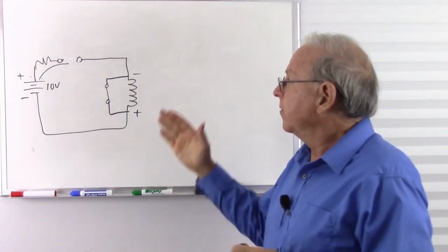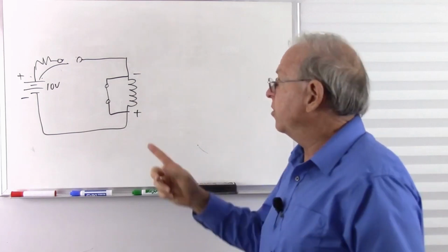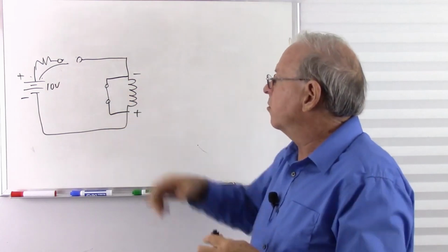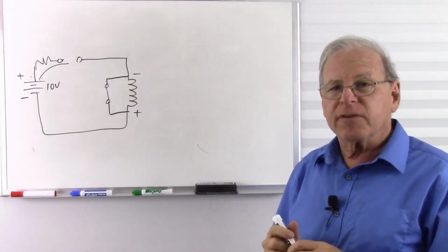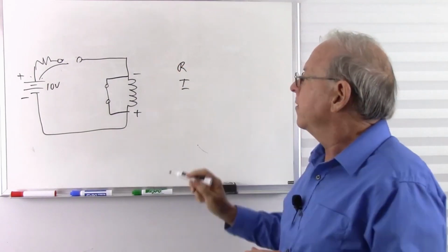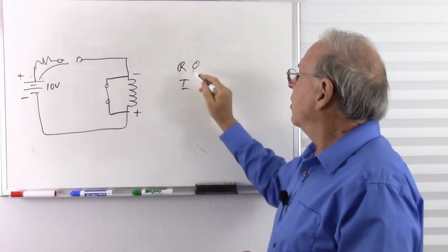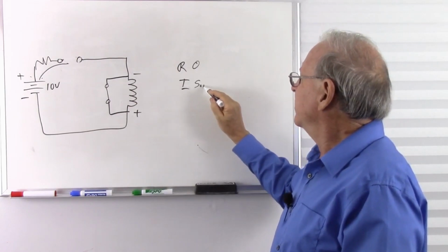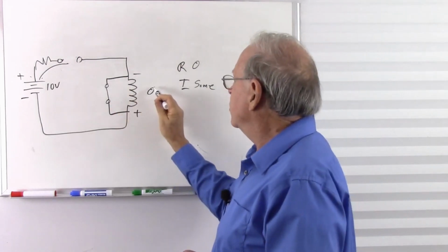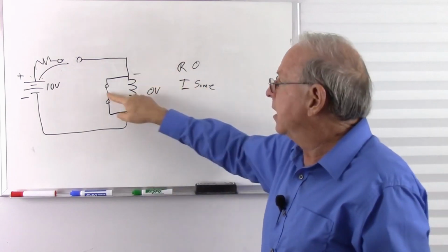So that's what a diode does. Polarize it one way, it's an open switch. Reverse the polarity of the voltage, it's a closed switch. So now when that is collapsing and the current is pushing, that becomes a short circuit. So how much voltage are we going to develop across a short circuit? Well, to get voltage we need two things. We need resistance and current. How much current do we have? I don't know, a lot. But how much resistance do we have? Zero. Zero times something is nothing. So we get no voltage, essentially. It shorts it out.